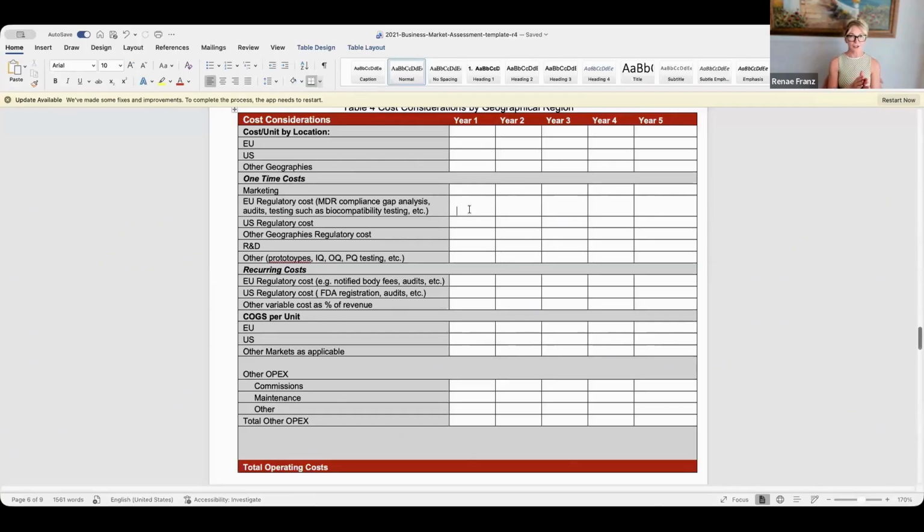And as the European regulations changed from MDD to MDR, they got up-classified from a class 2 device to a class 3. Not that the device did anything different, but they were in the pleural cavity. So it made it a higher classification, and they were looking at spending about $1 million to just keep their device in the market under the new MDR standards.